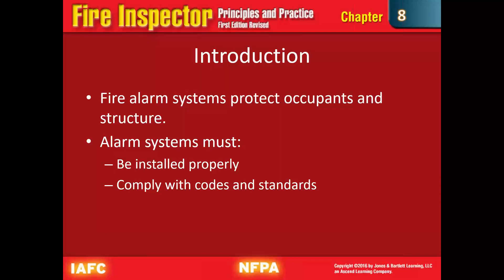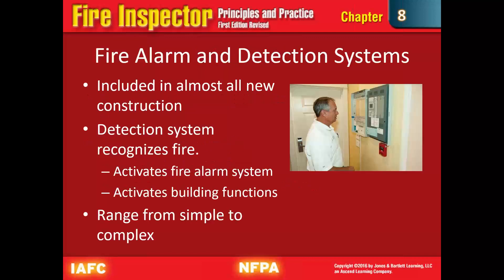Fire alarm systems must comply with the codes and standards for the jurisdiction and are included in almost all new construction, provided that they're required. The codes for each occupancy class lay out what occupancies require a fire alarm system based on occupancy load and type of operation. The detection system recognizes fire, activates the fire alarm, and can trigger various building functions — such as smoke doors, dampers, and HVAC systems — shutting off HVAC fans so they're not circulating and pushing smoke. Systems can range from very simple to very complex.